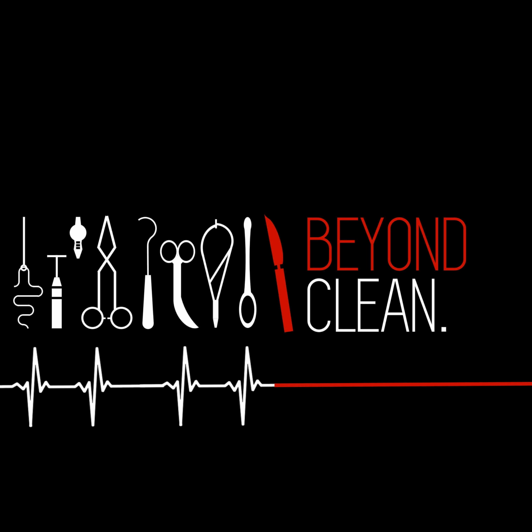Cytotoxicity is one of the most sensitive biocompatibility tests. And we'll see colorants fail cytotox because they're leaching, but the company is calling it medical grade because it's not a sensitizer, for example. But that's not really the whole story of what you have to prove for a medical device. So really it's important to understand what was being done on that colorant to make you feel good about using it in a medical device.